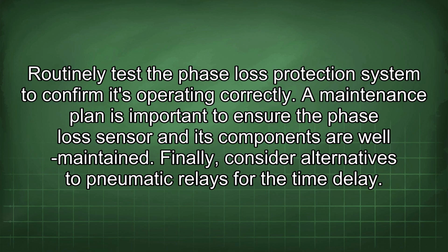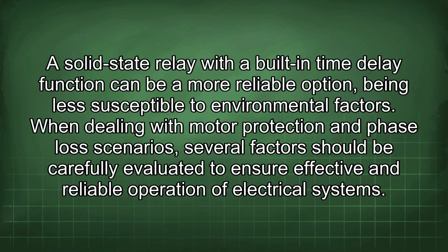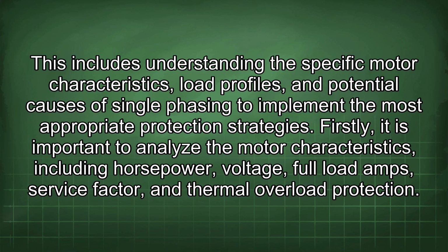Finally, consider alternatives to pneumatic relays for the time delay. A solid-state relay with a built-in time delay function can be a more reliable option, being less susceptible to environmental factors. When dealing with motor protection and phase loss scenarios, several factors should be carefully evaluated to ensure effective and reliable operation of electrical systems.